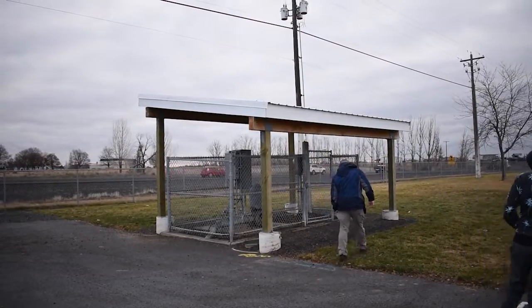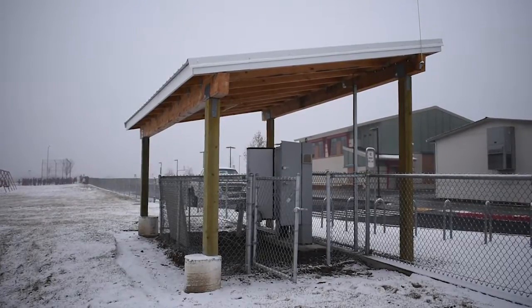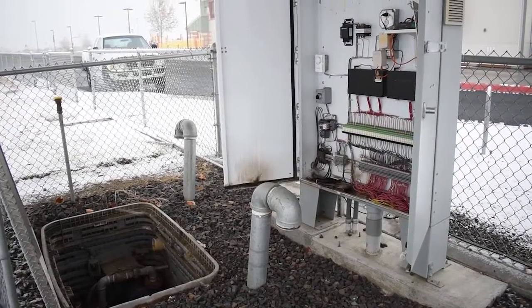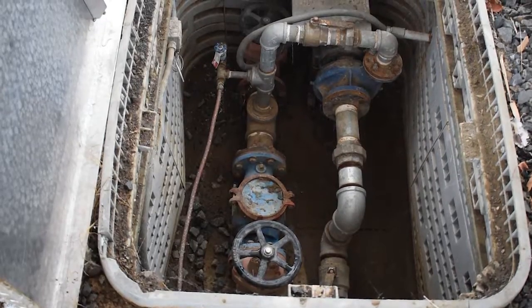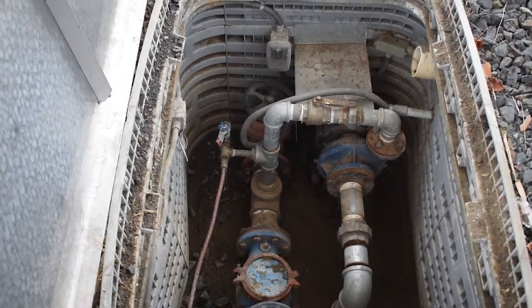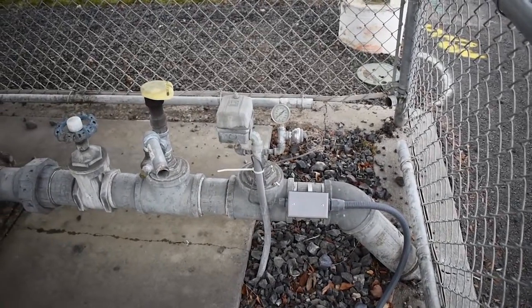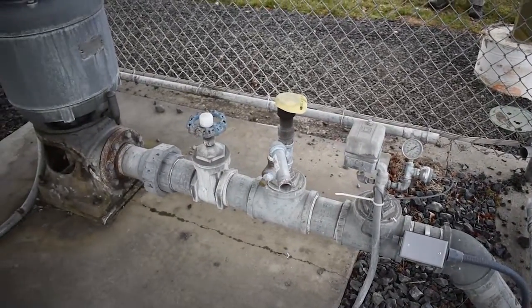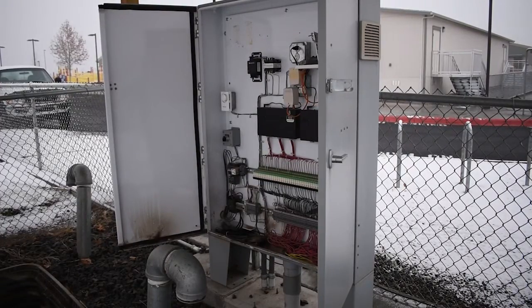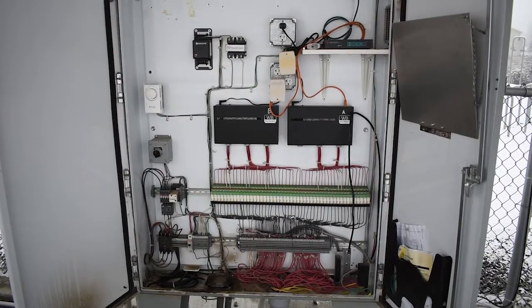The past several years, we have been modernizing our irrigation pump equipment. Our focus lately has been to add variable frequency drives to our well motors. This allows us to maintain a consistent water pressure, increasing water efficiency through our sprinkler heads, and reducing water hammer in the piping. All of our irrigation controls run through a system that we can access from anywhere we have internet service. This comes in handy when we get a call at 10 in the evening of a grass geyser flooding the school grounds — we can jump on the control system from wherever and shut the system down.